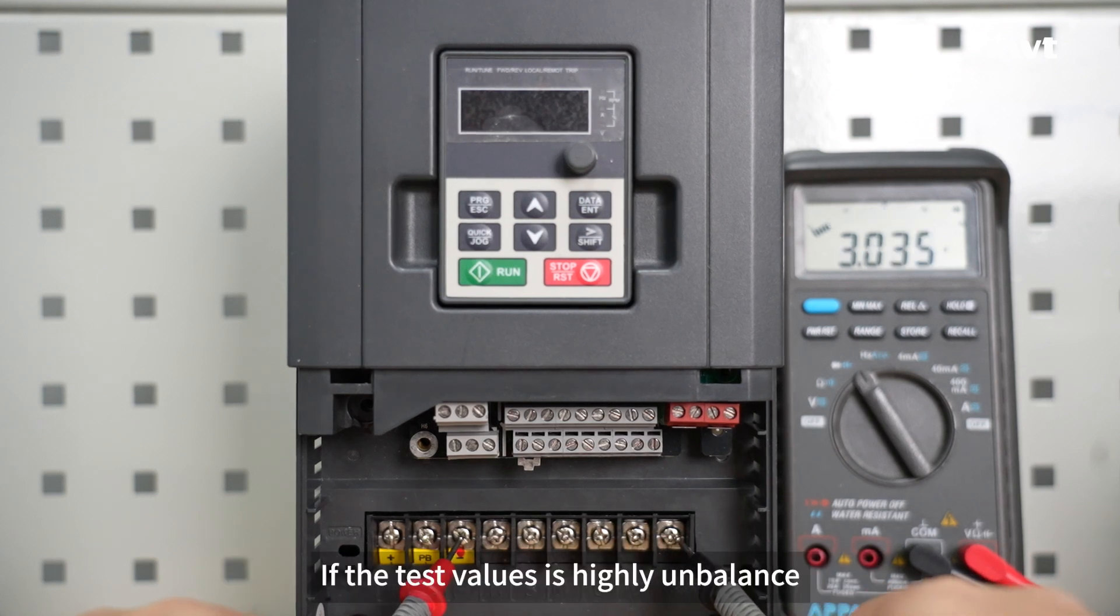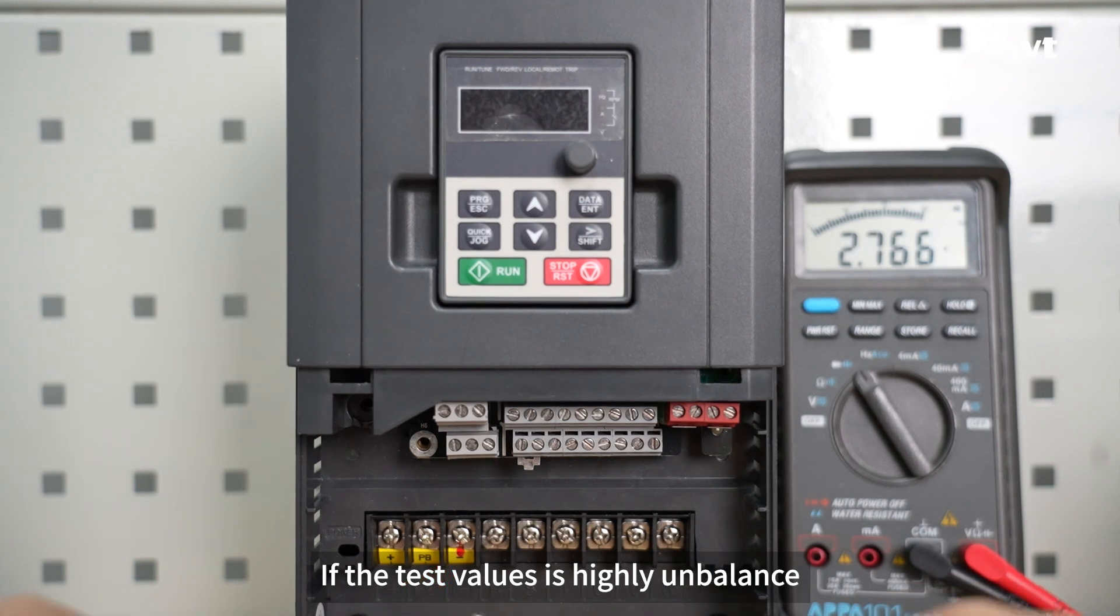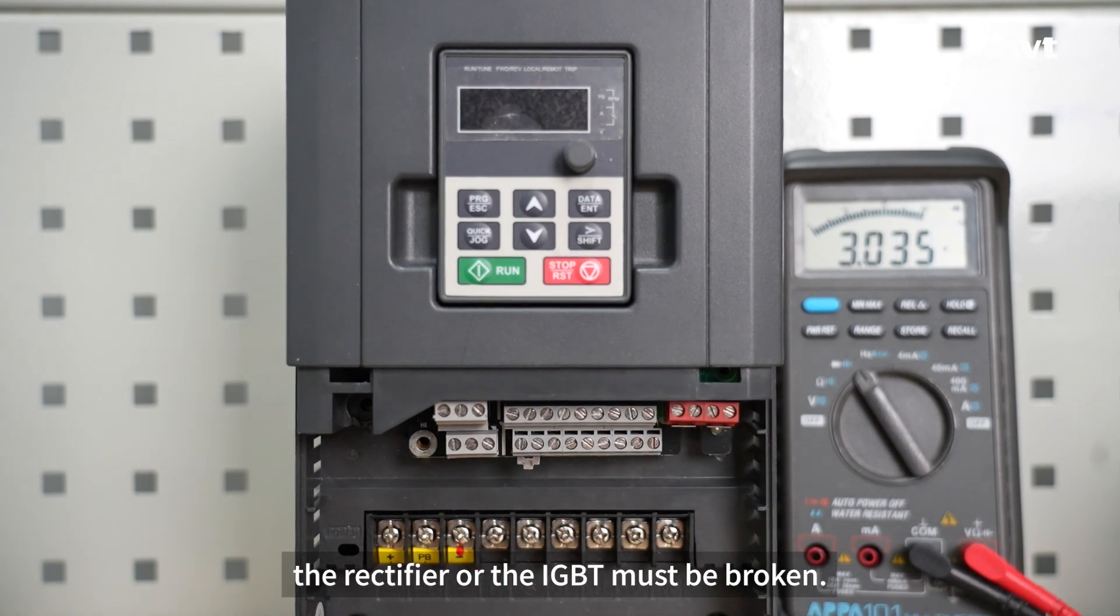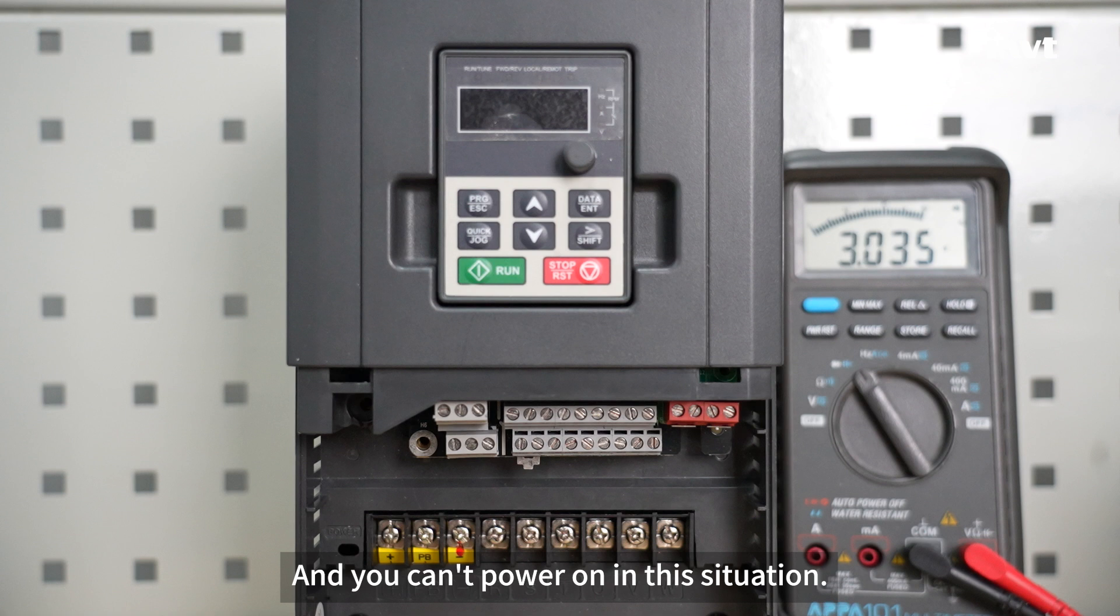If the test values are highly unbalanced, the rectifier or the IGBT must be broken, and you cannot power on in this situation.